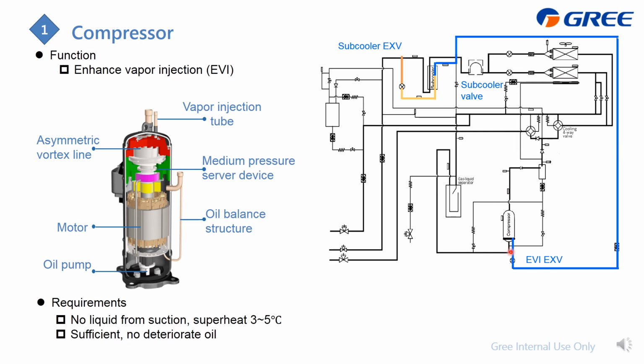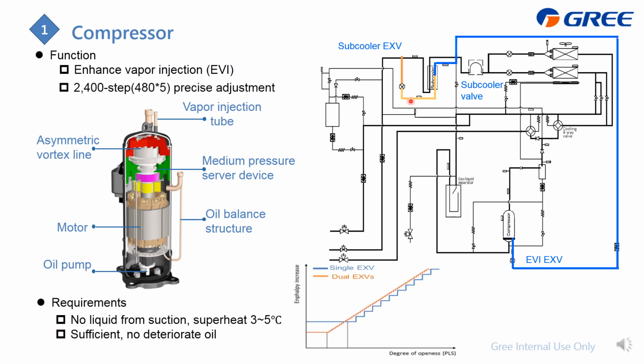And also, you can find that there are two EXVs controlling how much we need to inject into the compressor. This one, the subcooler EXV, is 480 steps. For this one, it is only 5 levels, although fully it is 480 steps. With this combination, we can achieve 2,400 steps to precisely control the injection amount. And with two EXVs, we can not only achieve the dedicated control just like this graph, but also lower the injection amount just like this.